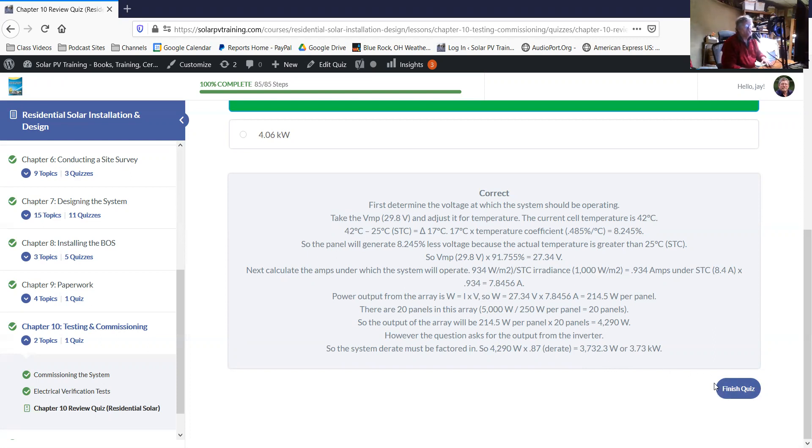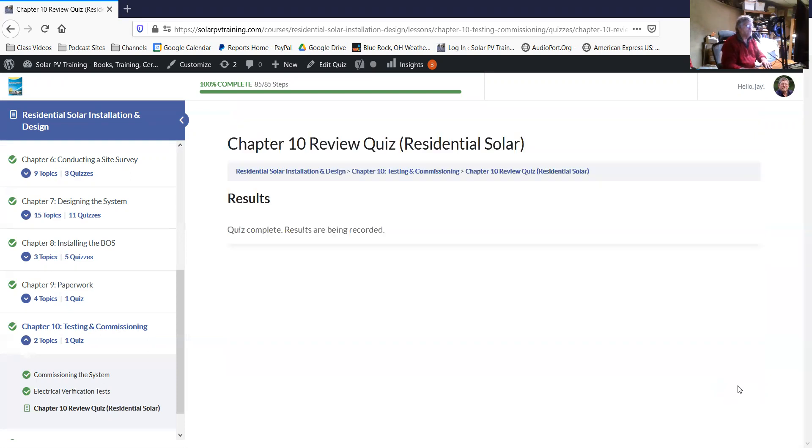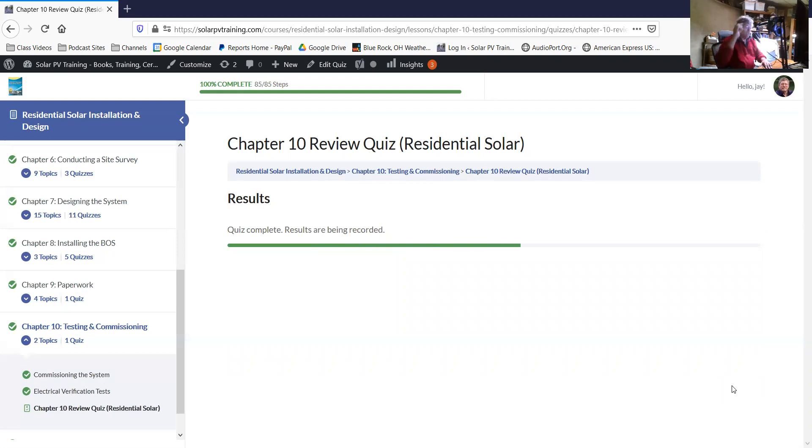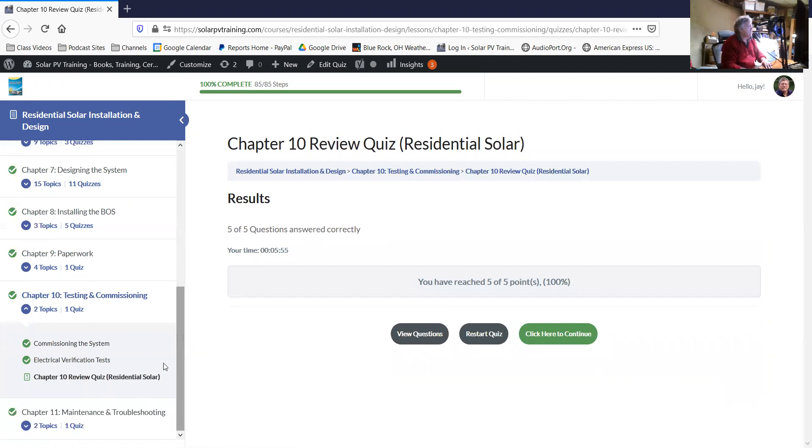This can be a sticking point because your customer might say, hey, you said this was a 5kW system and it's only producing 3.7. Well, that's because of the conditions and it's a 5kW DC production, but the AC production has to be derated for a number of factors. So try and make sure you level set that ahead of time so that they don't expect that they're going to be getting 5kW of production at all times.